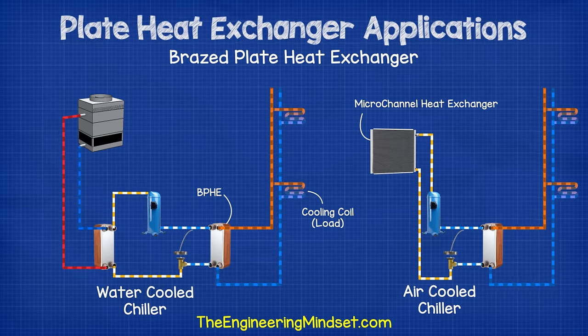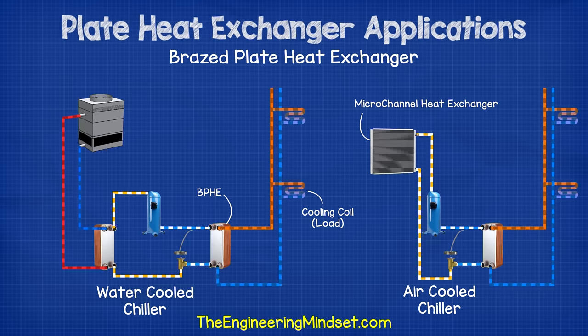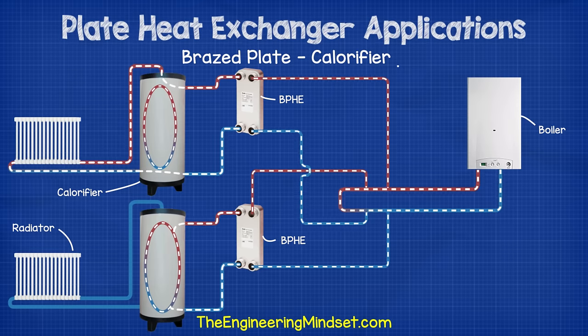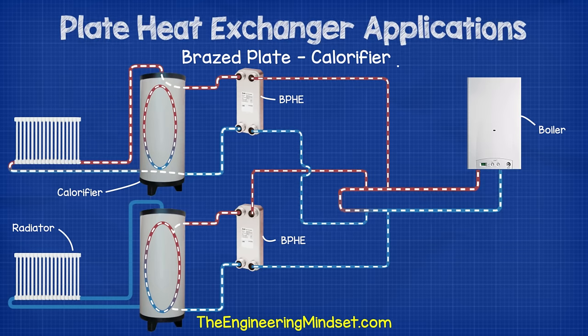Chillers have begun to be produced using brazed plate heat exchangers. On an air-cooled chiller, the evaporator can often be replaced with a brazed plate type, and in water-cooled chillers both the evaporator and condenser can be replaced with brazed plate type, depending on the size of the cooling load. Calorifiers and hot water tanks are also often indirectly connected to heating circuits through brazed plate heat exchangers, allowing instantaneous hot water or storage vessel draw depending on the building's demand.